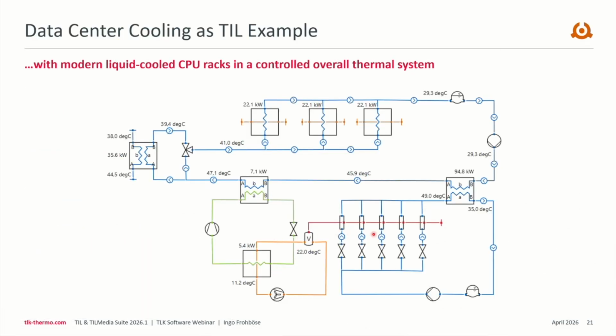Here you see these modern liquid-cooled CPU racks in the middle of the system, controlled by an overall thermal system. We have an inner cycle here with a pump and different valves to cool down the CPUs, and another cycle to bring the waste heat to a local heating system to recover part of the wasted heat.